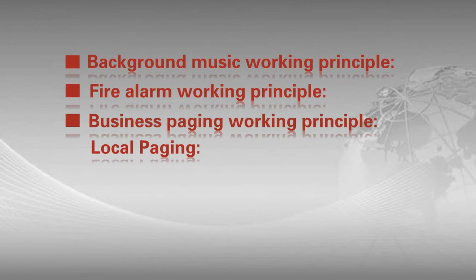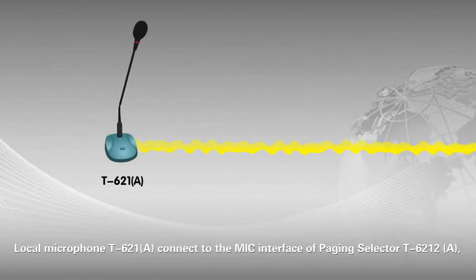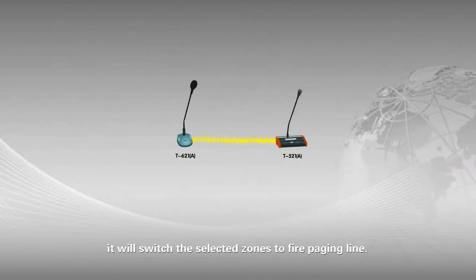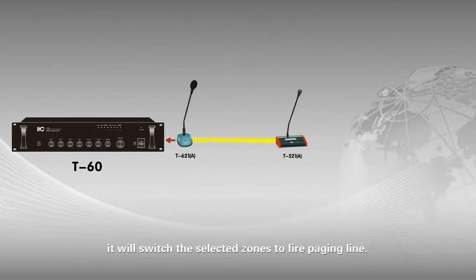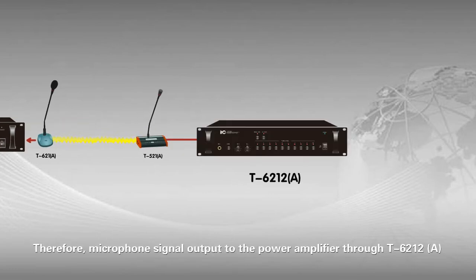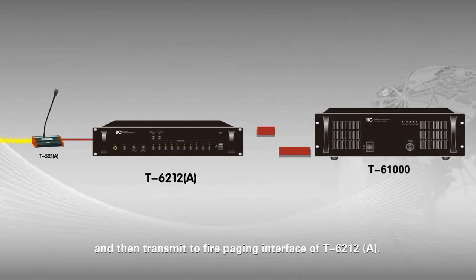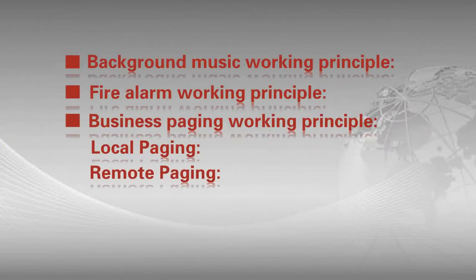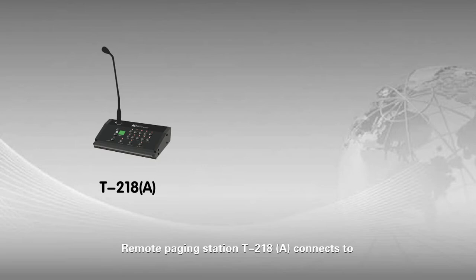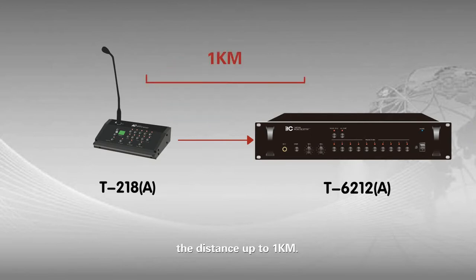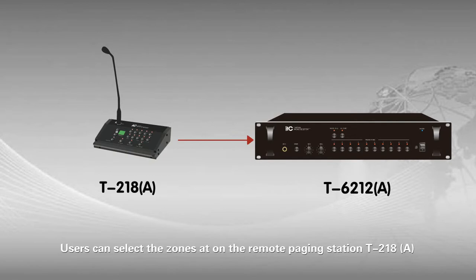Business paging working principle. Local paging: the local microphone connects to the mic interface of paging selector T6212A, then the zone to broadcast is chosen manually, switching the selected zones to the fire paging line. The microphone signal outputs to the power amplifier through T6212A and then transmits to the fire paging interface. Remote paging: remote paging station T218A connects to paging selector T6212A via network cable up to 1000 meters; users can select zones on the remote paging station T218A directly to broadcast.